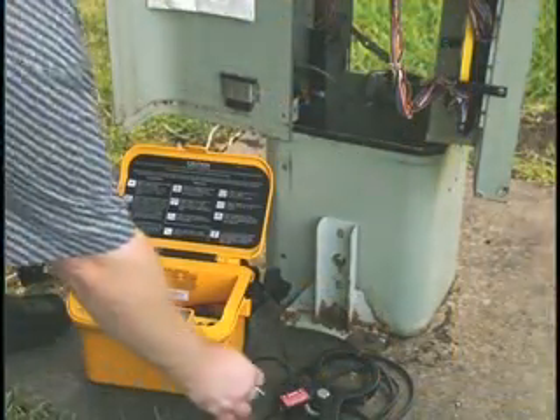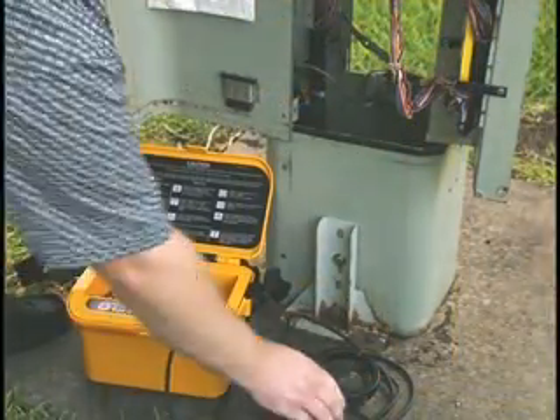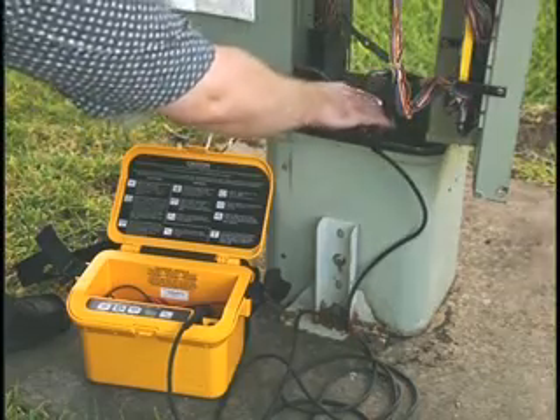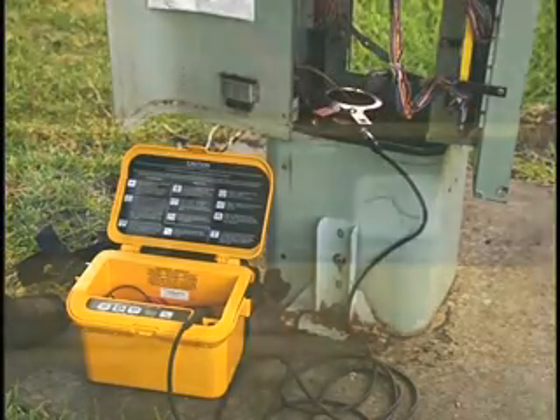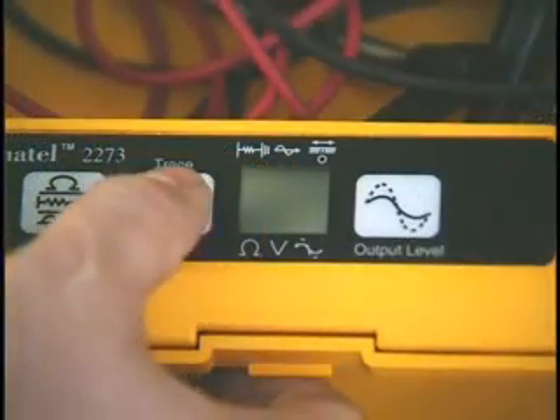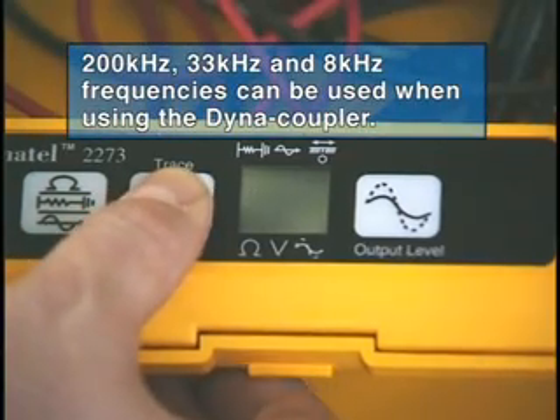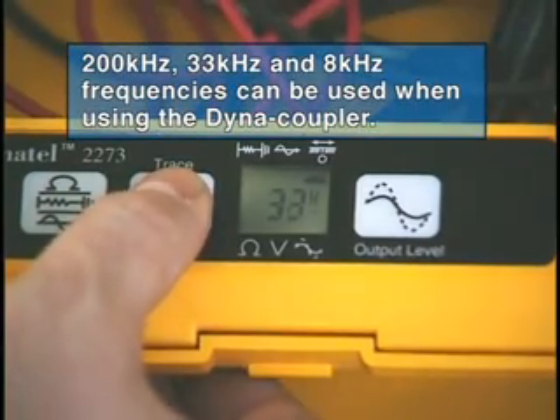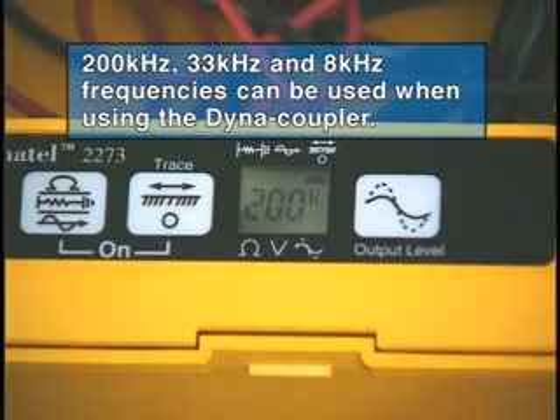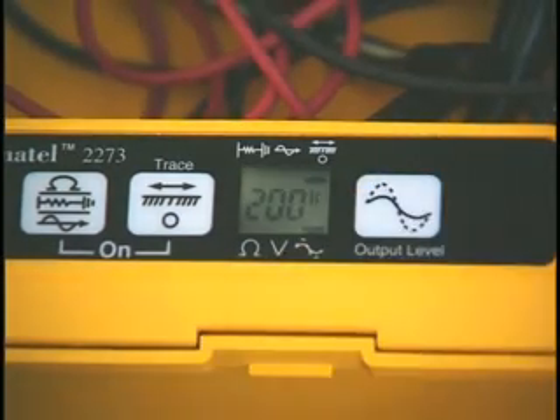The Dynacoupler connects to the output jack with its own cable, and it's then clamped around the conductor you want to trace. Press the trace key and select the 200 kHz frequency. You should also use high power with the Dynacoupler, so press the output level key to select high output power.